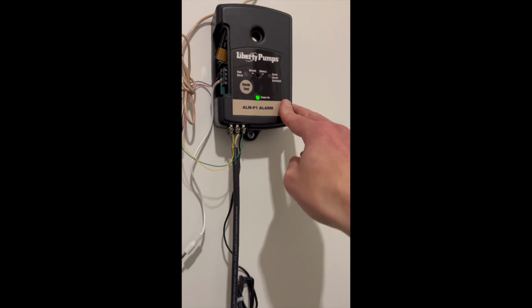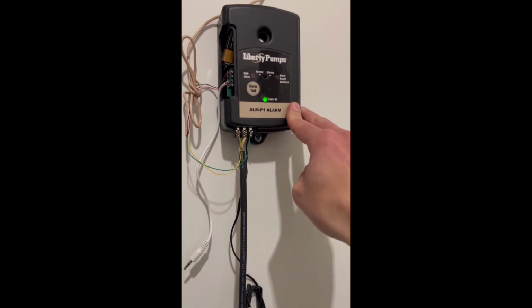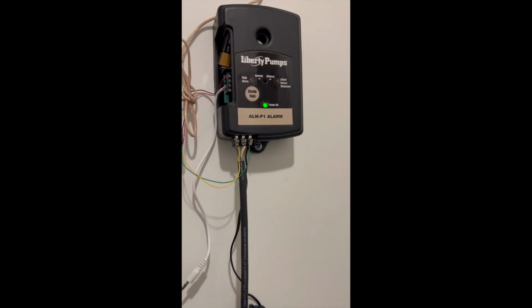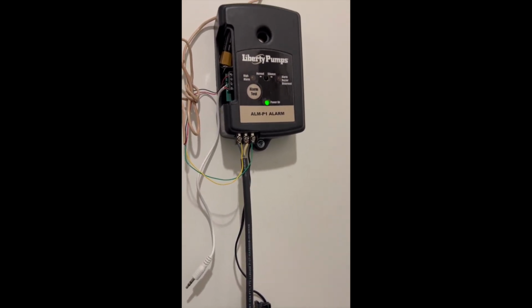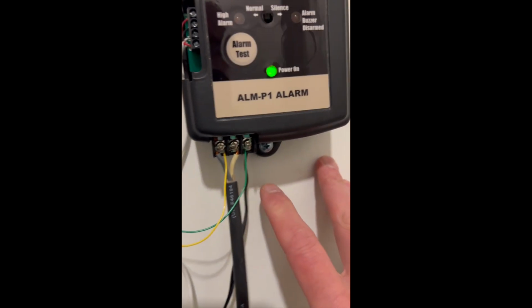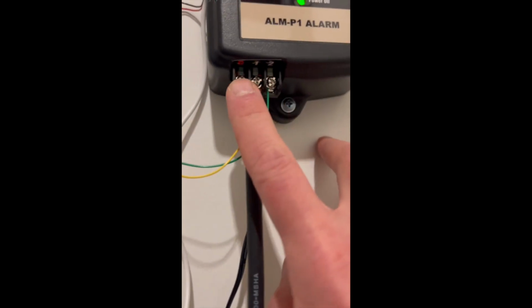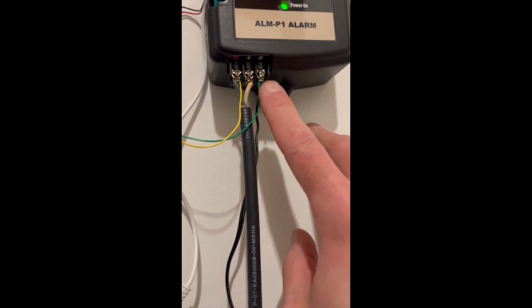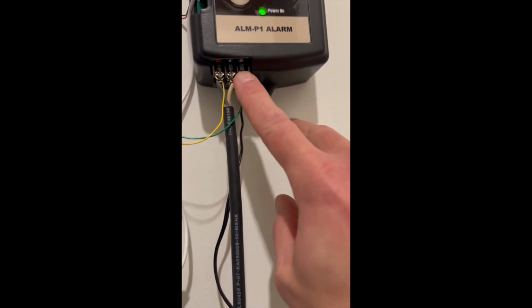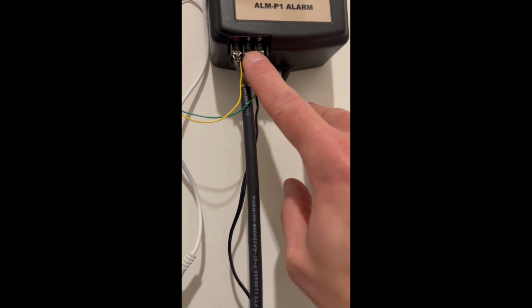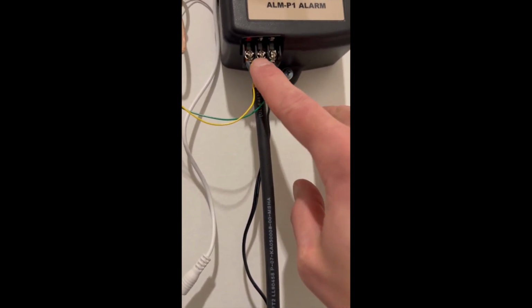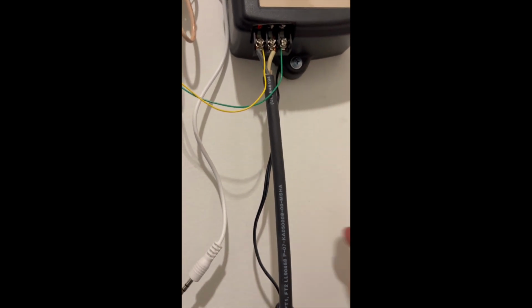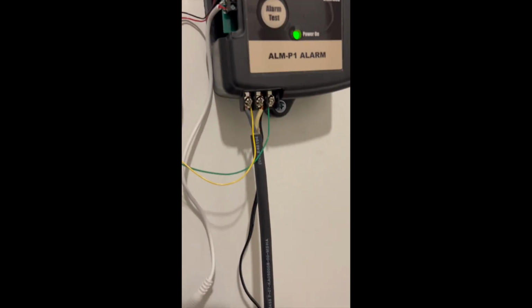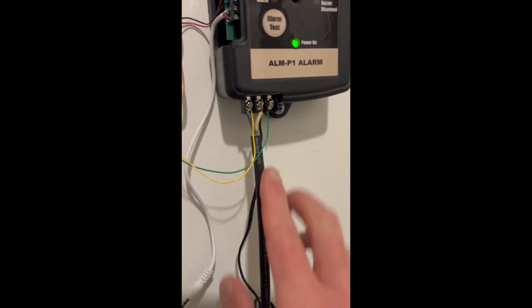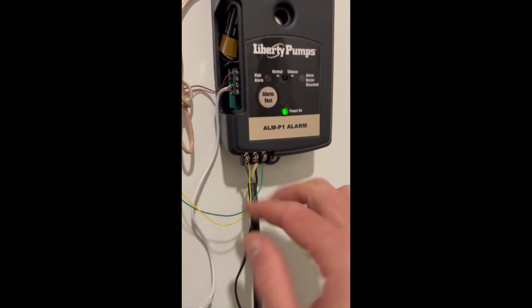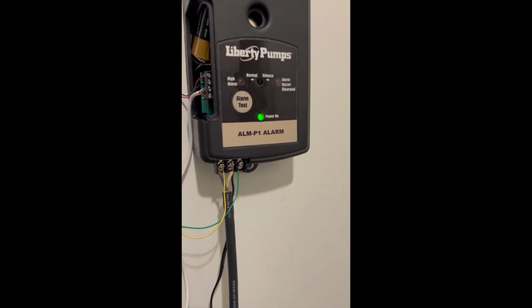Now, a lot of companies make these types of alarms. There's nothing particularly unique about this Liberty version over probably another. The way that this alarm is designed is it has a common and then 2 alarm inputs. It doesn't really matter. These are just on the same trace inside the alarm. They're essentially shorted to each other, so I could just as easily put 2 wires on this one rather than separate them. Doesn't change anything. So what happens is the alarm float triggers, essentially shorts these two contacts. This alarm beeps, makes a very loud noise.